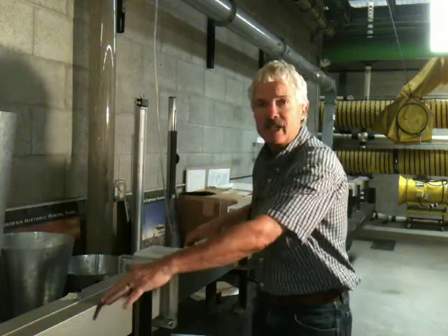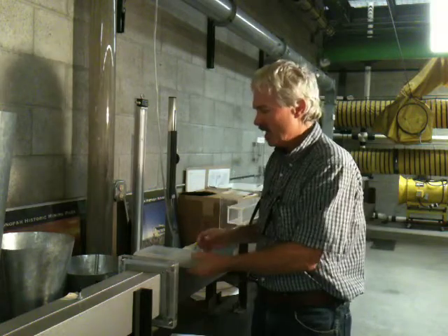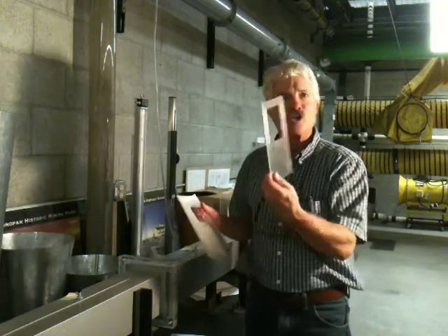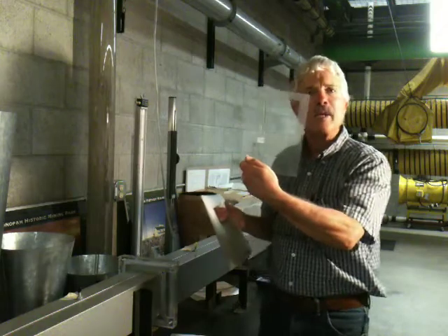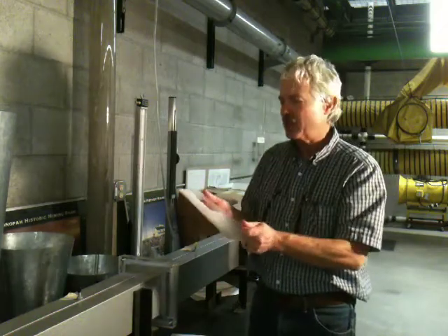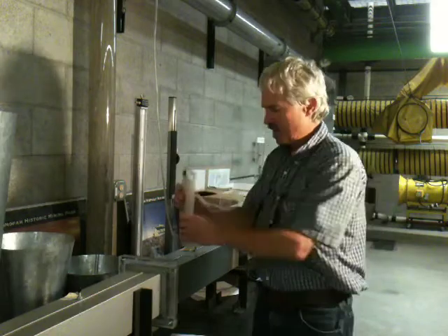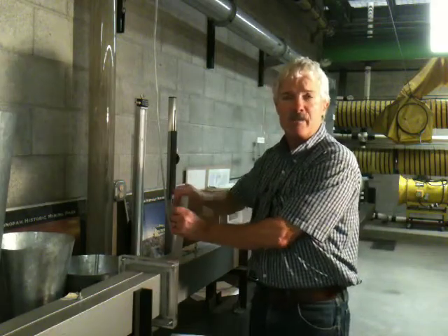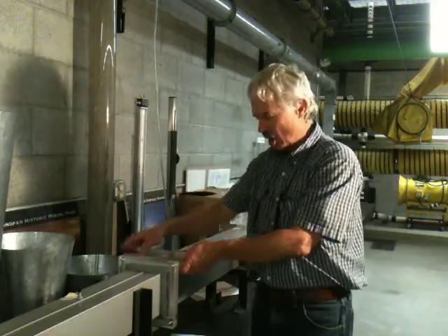The second exercise we're going to do is to actually look at the shock loss across the regulator station. So remember, shock loss occurs whenever airflow changes direction. For example, with the larger size of regulator opening, there's not going to be a lot of obstruction, probably not a lot of shock loss, whereas with the smallest panel, there's going to be quite a bit of obstruction and therefore quite a bit of shock loss. Okay, moving down.